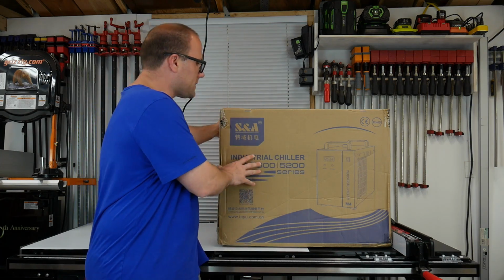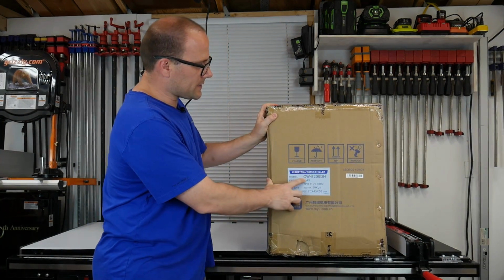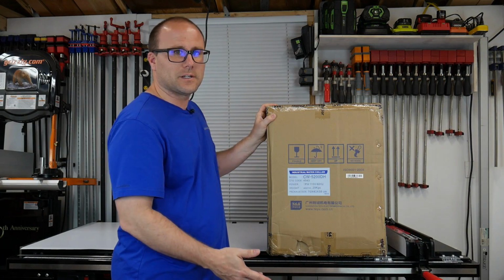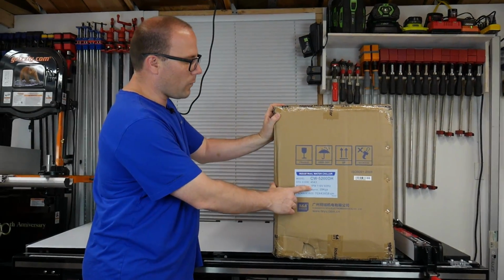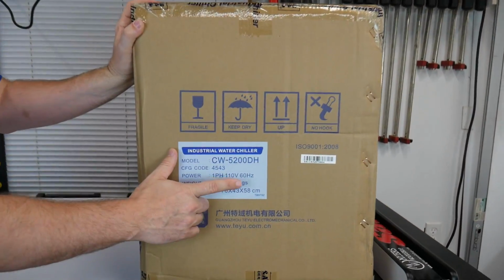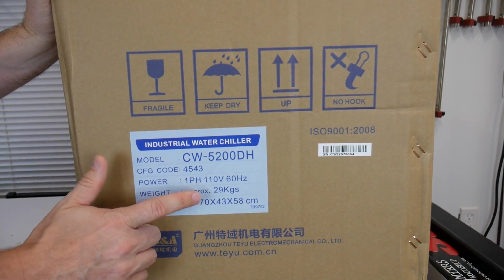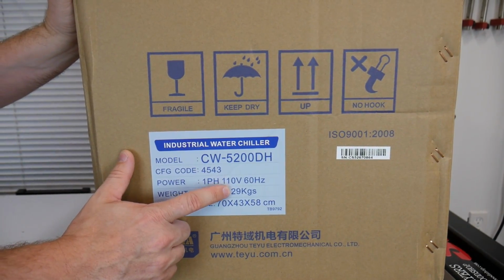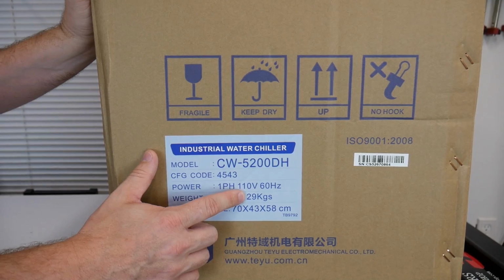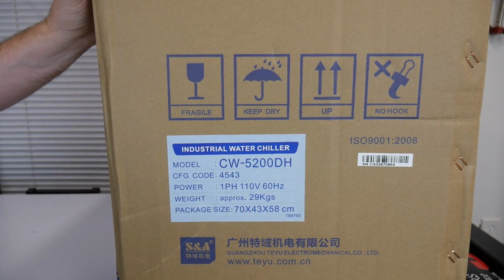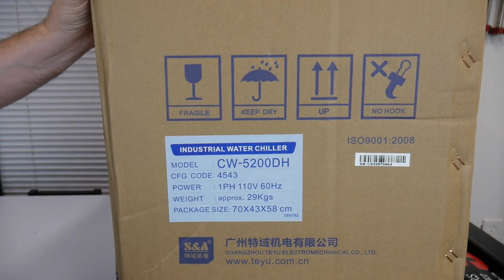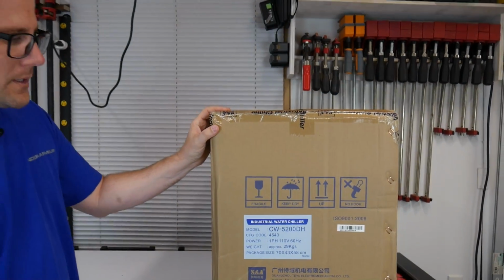Now you'll notice on the side, I'll turn it around, this is a CW-5200 DH. Because of that, it's single-phase, 110 volt, 60 hertz, and that is really good. Make sure you get one that's the correct wattage and voltage for your shop or wherever you're storing this. We don't have 220 in this shop, so we got the 110.